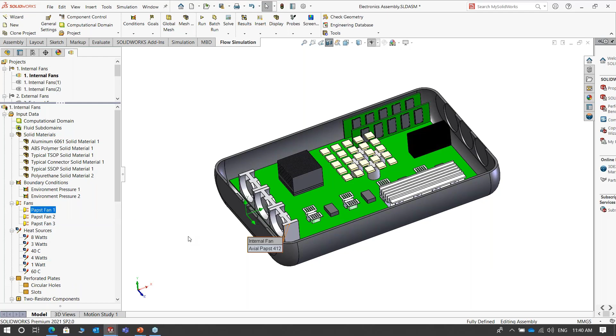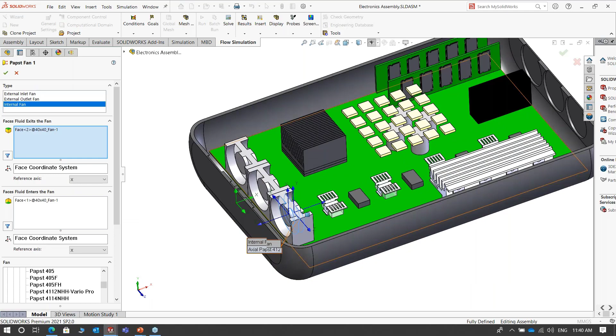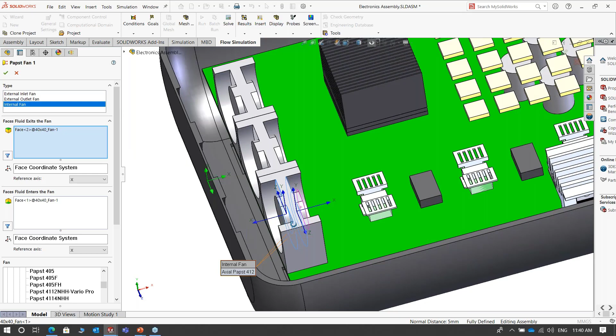In this case, as I said, it is making use of internal fans. The first configuration is making use of the internal fans, where we just have to provide the exit and entry of the fluid inside the enclosure. And when it comes to the library, this is what I was talking about in my slides, where it has all the values with respect to fan curves for all of these fans. These are commercially used fans for electronic applications. However, if you have your own fan curve, this library can be customized to meet your requirement.